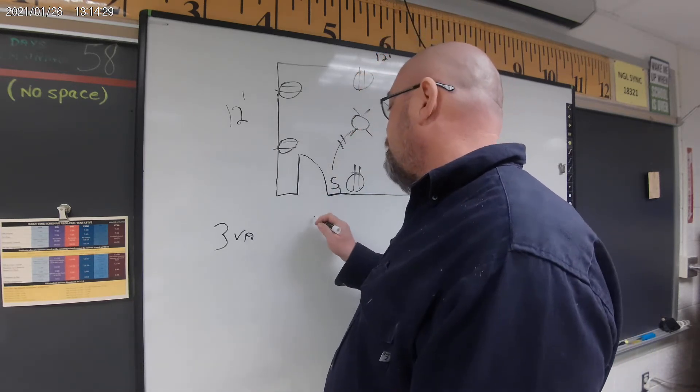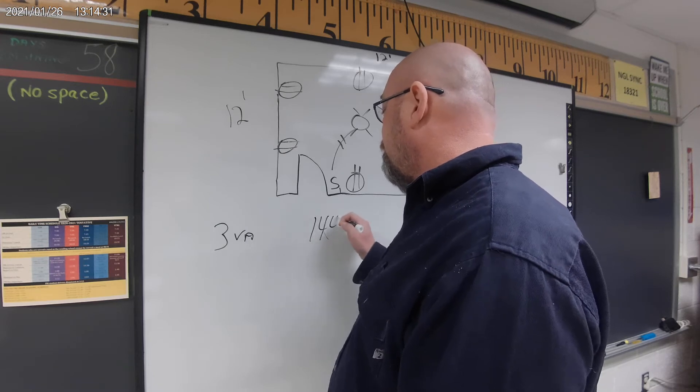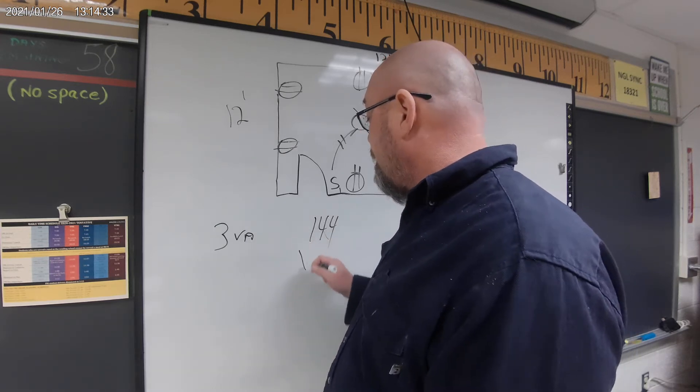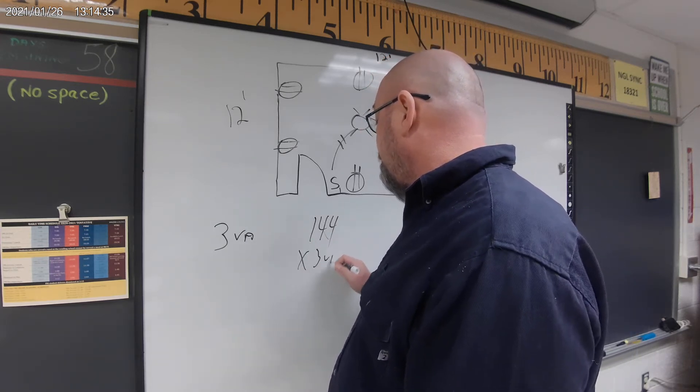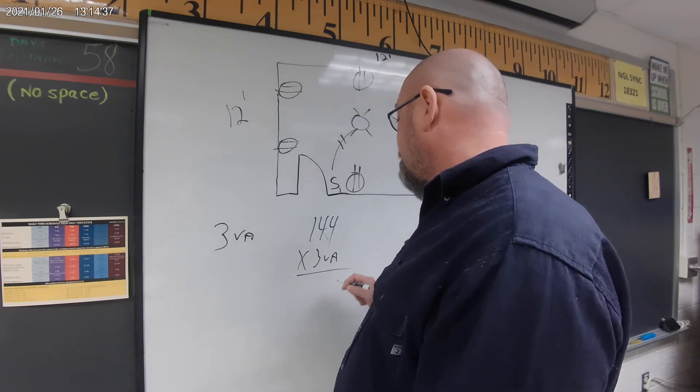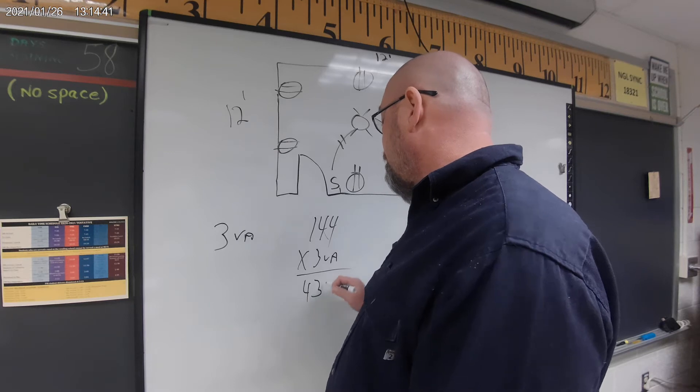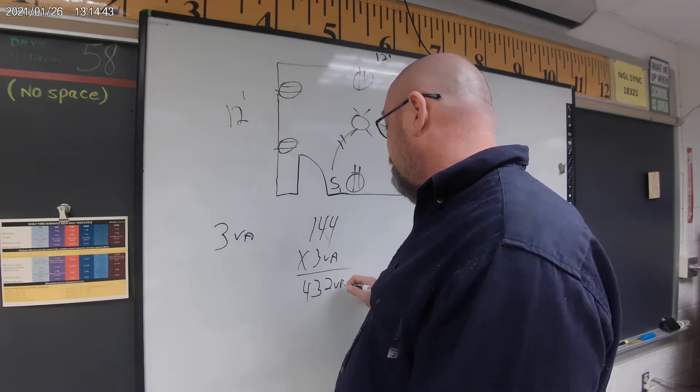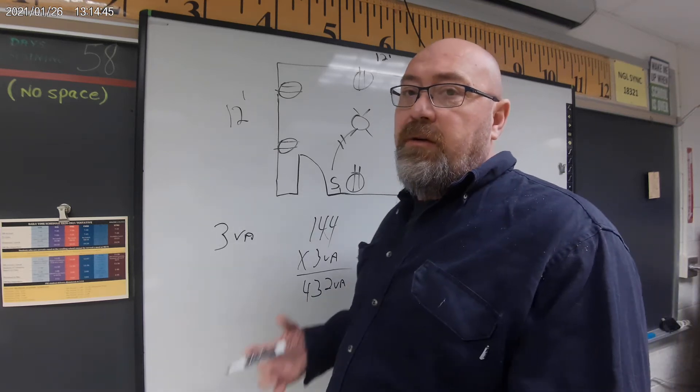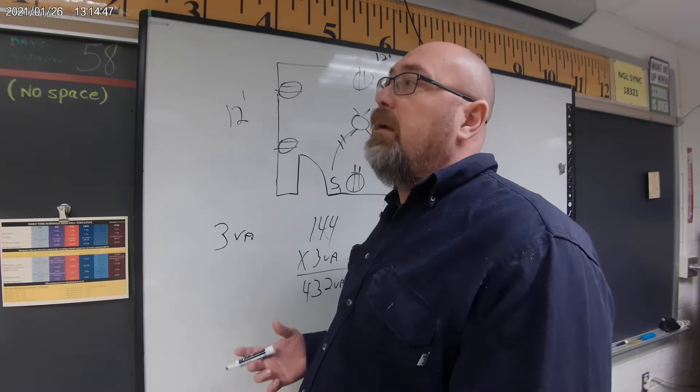That comes out to 144 square feet. I times that by my three volt amps, and that is going to come out to 432 volt amps. Now we want to calculate that into our amperage.